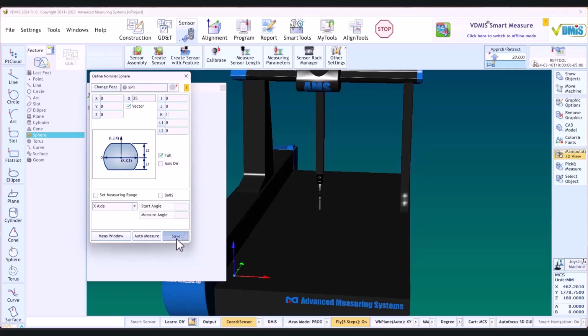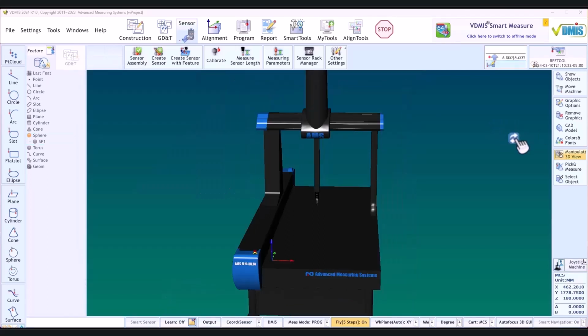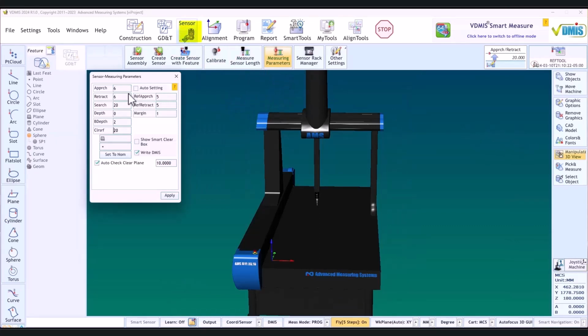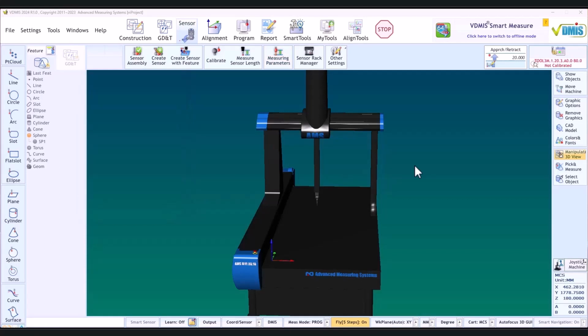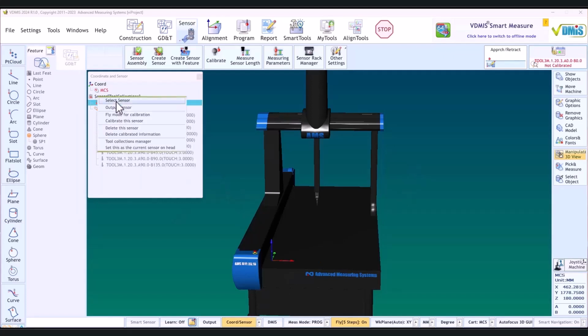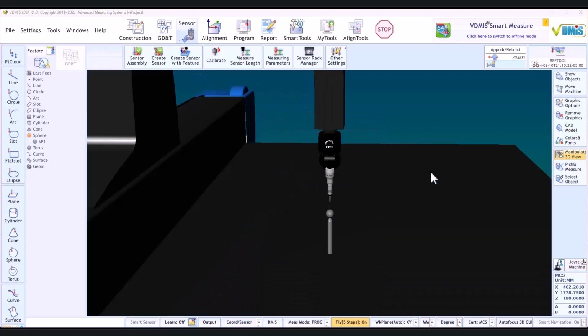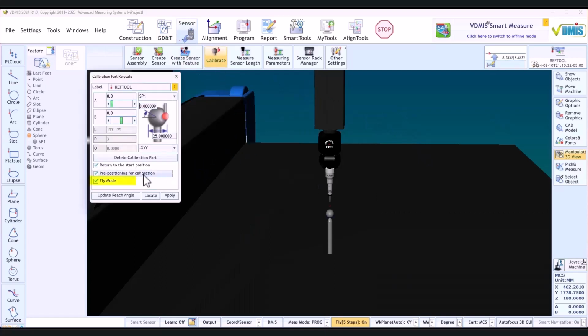Before starting the calibration, it is recommended to check the measuring parameters to make sure they are the right parameters for the calibration. We recommend 6 mm for approach and retract, 20 mm for search and clear surface. To locate the calibration sphere, we select the reference tool from the sensor database. Then we position the sensor above the calibration sphere, click on the button Calibrate in the sensor toolbar, make sure the fly mode is checked, then click on the button Locate.